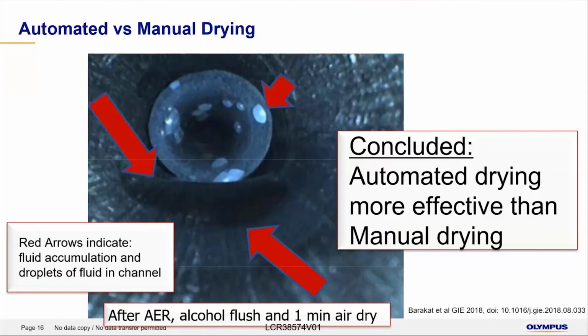It's pretty clear that if you look at the FDA data, they have indicated that about 5% of high-concern organisms are cultured from endoscope channels when they take them right out of the AER and take samples and culture them. What this means is that in at least 5% of the scopes in the United States, there are organisms still in these channels. And if that's in the presence of moisture, they will definitely be able to replicate during storage and potentially form biofilm.